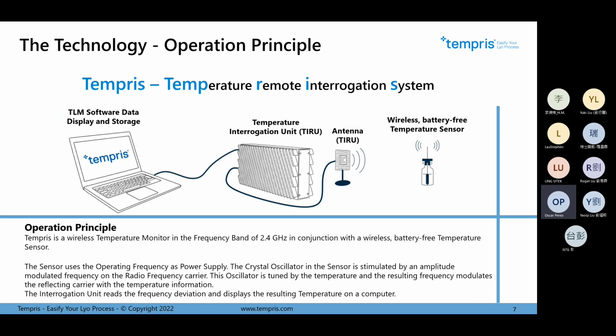It's getting the energy by radio frequency, and the oscillation it undergoes is directly proportional to the product temperature. So depending on the temperature of the product the sensor is submerged in, this oscillation changes. This behavior is carried by the antennas to the system, and the system converts this oscillation into a very accurate temperature. I say very accurate because we are talking about the complete system: antennas, interrogation unit, and sensors. We offer as standard an accuracy of plus or minus 0.7 Kelvin or Celsius degrees, and we can also offer 0.5 and 0.3.